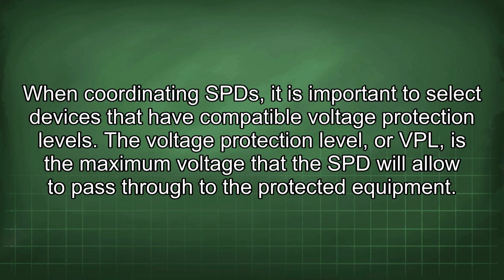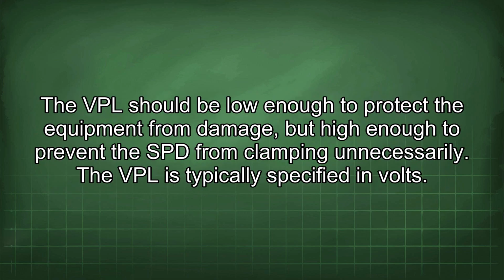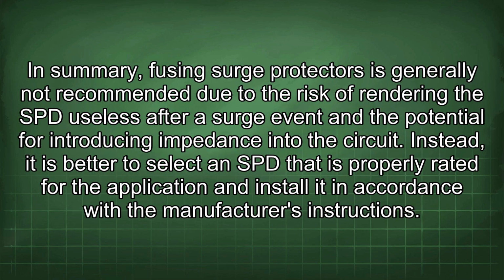The voltage protection level, or VPL, is the maximum voltage that the SPD will allow to pass through to the protected equipment. The VPL should be low enough to protect the equipment from damage, but high enough to prevent the SPD from clamping unnecessarily. The VPL is typically specified in volts. In summary, fusing surge protectors is generally not recommended due to the risk of rendering the SPD useless after a surge event and the potential for introducing impedance into the circuit.